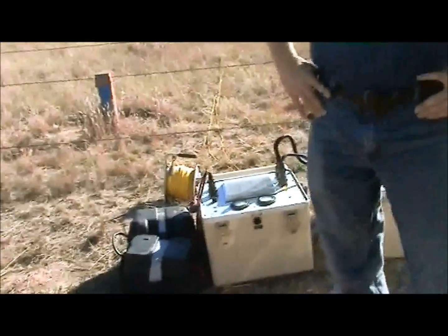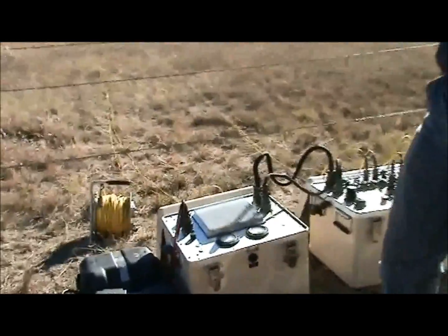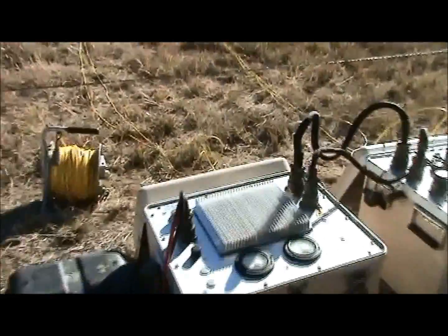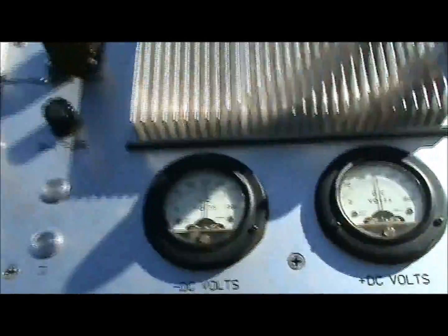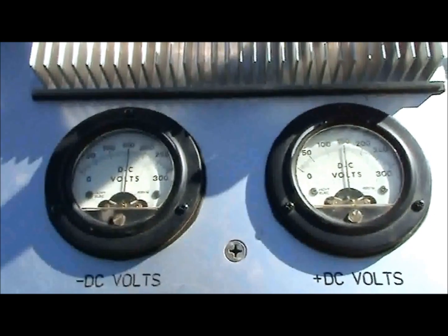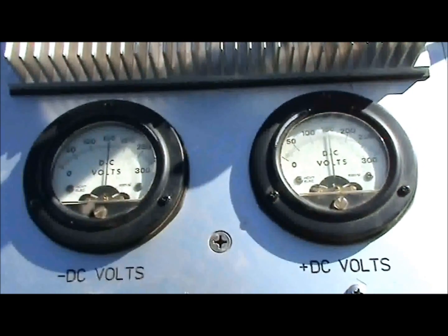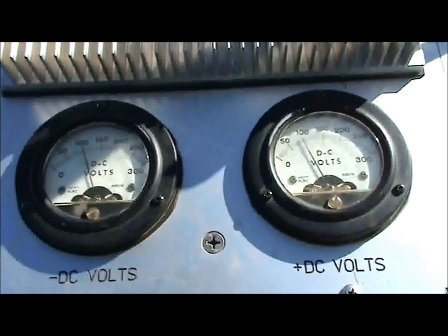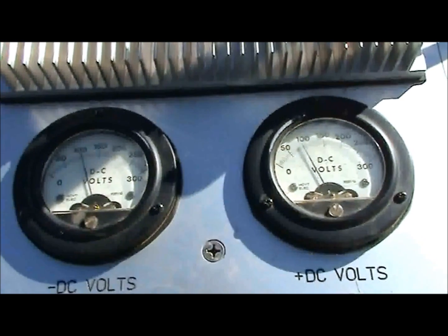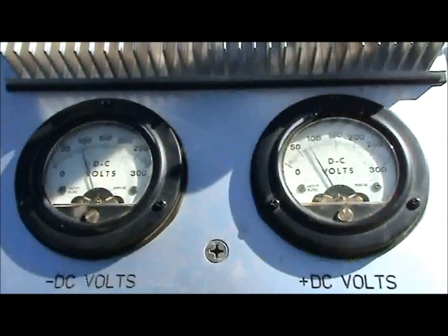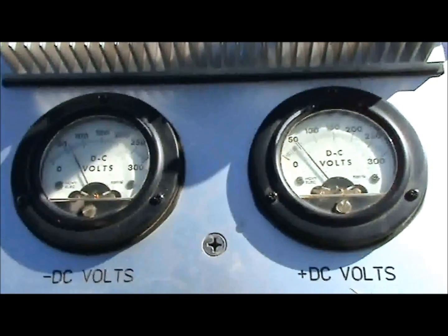So NMR also starts at the highest pulse moment. Let's take a look at the bus voltage here before it starts its next run. If you keep an eye on the voltmeters there, they're starting up at about 150 in this case. And there it goes, down the first set of CPMG pulses. And so you get the idea.